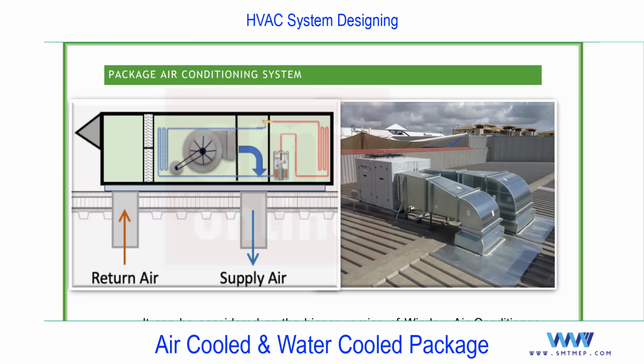And the difference between air cooled and water cooled system, we discussed this point at the time of the vapor compression cycle. If the condenser is cooled by air, that system can be a package or can be a chilled water system. That we'll discuss next, after completing the VRF and other systems. So if the condenser is cooled by air, that system we can call an air cooled system.